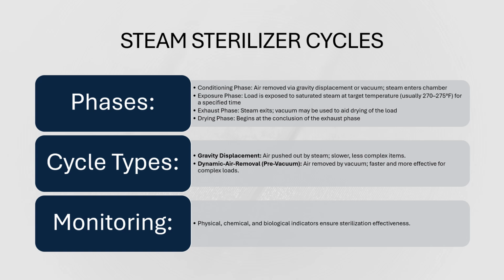After the exposure phase, there is the exhaust phase. This is where steam is removed, and this is where the drying time begins. Pre-vacuum steam systems use a vacuum during this phase to improve drying, which is critical to maintaining the sterility. Each cycle must be monitored using physical, chemical, and biological indicators to confirm the sterilization parameters were met and the cycle was effective.